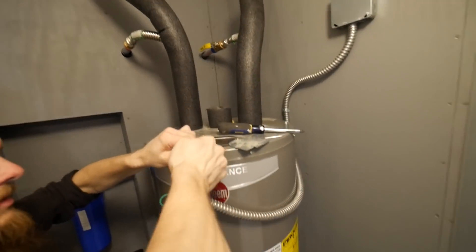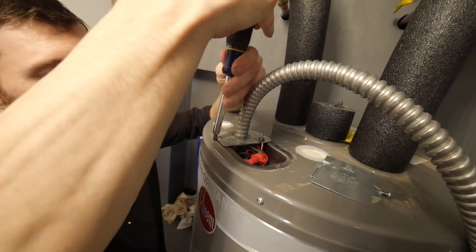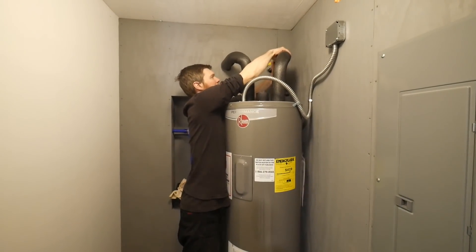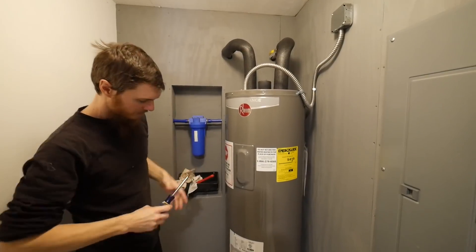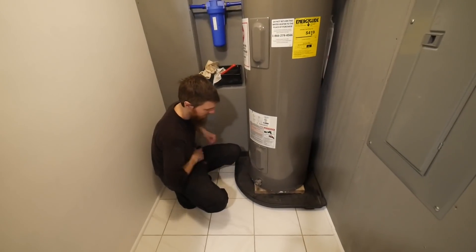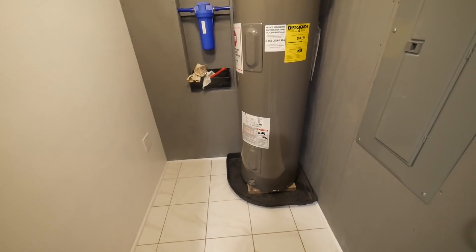Okay, make sure they're tight. I wanted to put a strap on here — I was going to take this screw out and put a strap on there, I wonder if I have one. We don't see any leaks so I'm going to go ahead and close this foam up the best I can, probably should wrap it with tape later. I'm happy with how it all looks. The blocks I think support it enough — I like that they raise it up a little bit, it just makes it easier to get a hose on here. And if water does get in here, at least the metal isn't sitting in it rusting.